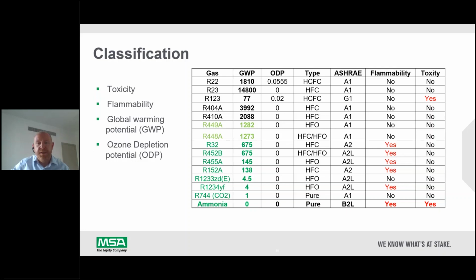So this shows you some of the new gases and really the change in the old gases as well. So you can see the ozone depletion potential has decreased to 0 over time. And the GWP is starting to come down as well. But what's happening is, you can see here, there's more red in this table. So more of these gases are getting more flammable, either with an A2 or A2L category, which increases the risk for the owner and the operator of these systems. And the designers of these systems need to be aware that these dangers are there.